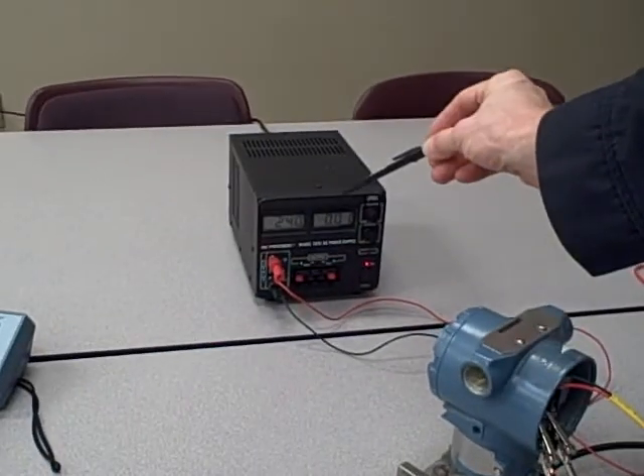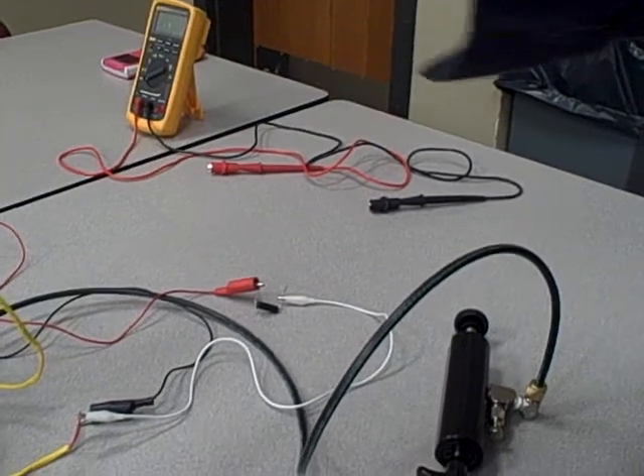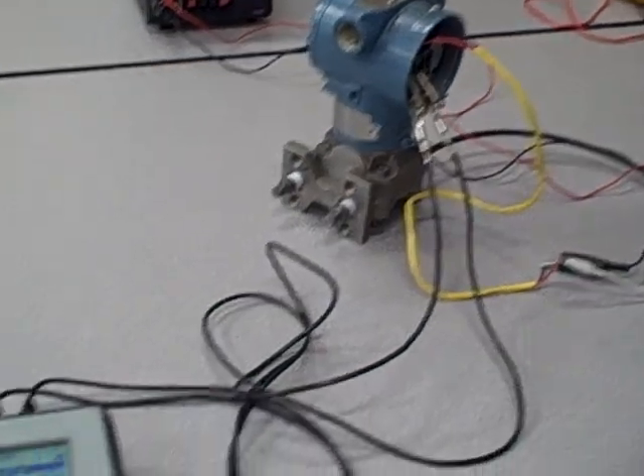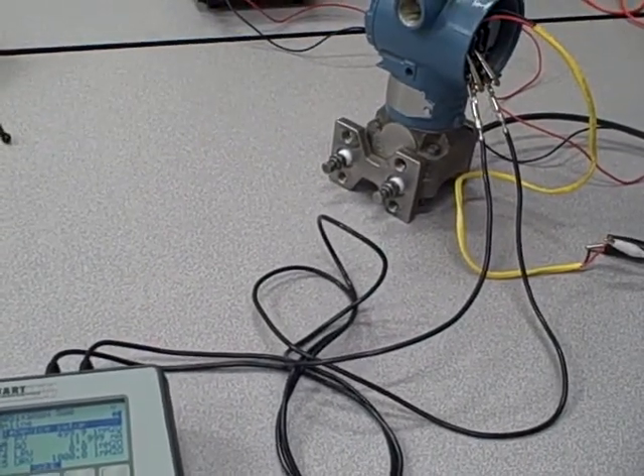We're powering it through a 24 volt power supply, through a 250 ohm resistor, right to the transmitter. And currently we have the communicator connected in parallel with the transmitter. This is the most standard method of connecting the communicator, directly in parallel with the transmitter terminals.